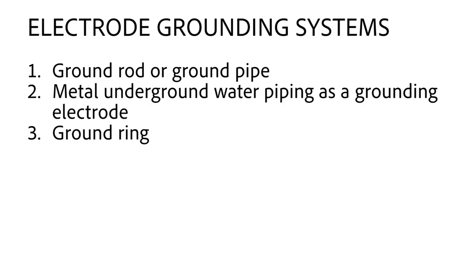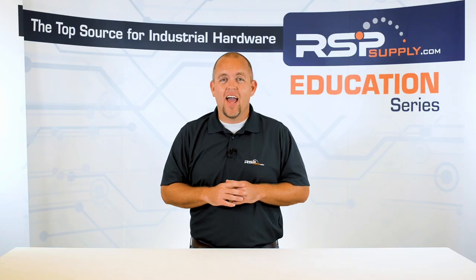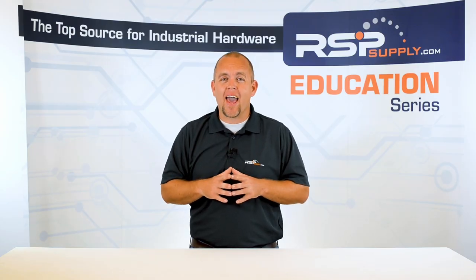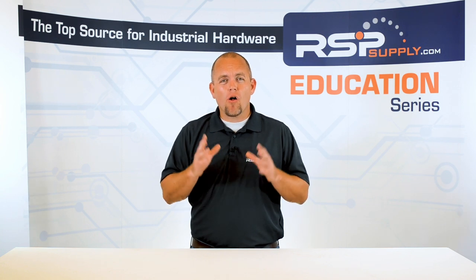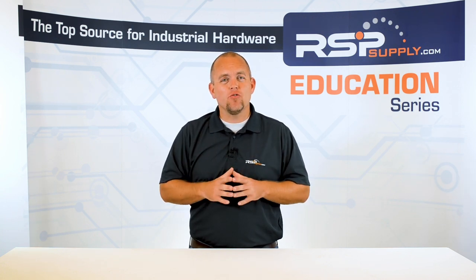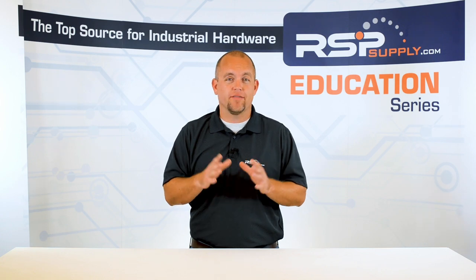Next is the ground ring, which we discussed in our last video. A ground ring is simply a conductive material such as copper that surrounds any given structure. It is required that the wire used be no smaller than two gauge wire and that the wire is buried at least two and a half feet below the surface. There are other grounding techniques that can be used with this method to increase its overall effectiveness.